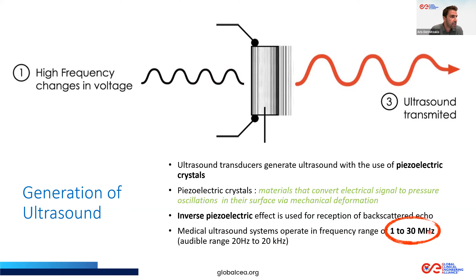So the probe is made of a series of piezoelectric crystals, one next to the other. We have a backing layer, an acoustic lens, a matching layer, and if you remember, we always use a gel. This gel is used in order to have the same acoustic impedance between the probe and the skin, and to avoid having any air between the skin and the probe, because if we have air, as we said, all the energy, the ultrasound wave, will be backscattered back to us. So we use the gel to avoid having air between the skin and our probe.